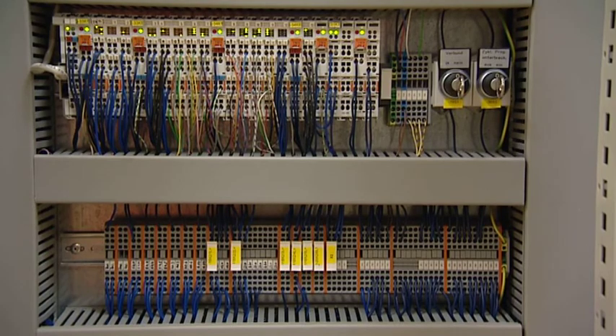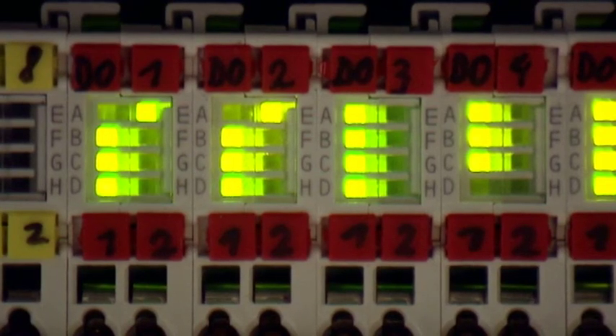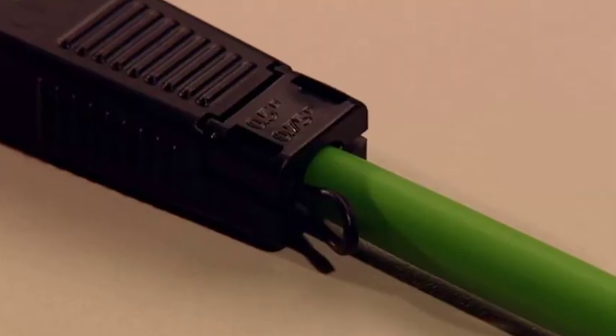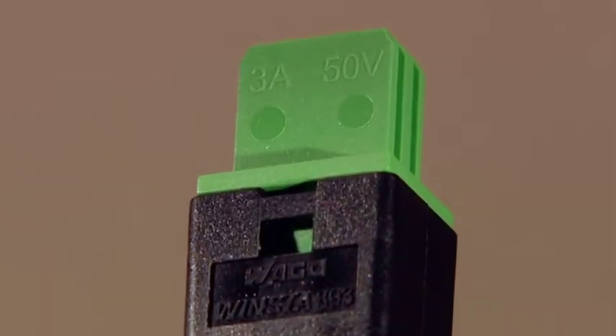Within building automation, WINSTA KNX is in charge of connecting the individual bus nodes — fast, safe and flexible. WINSTA KNX is suitable for single wire conductors with a diameter of 0.8 or 1 millimetres. Current carrying capacity is 3 amps.